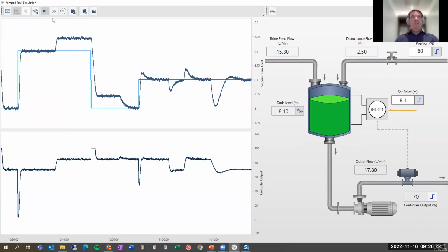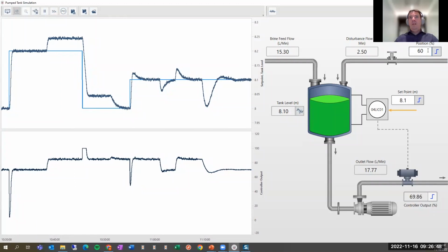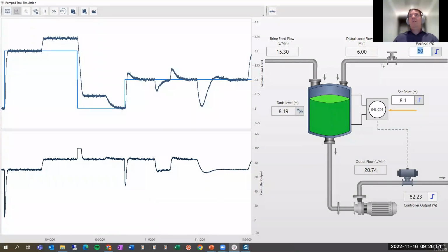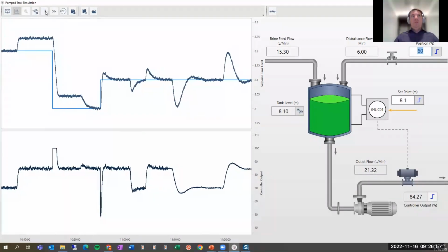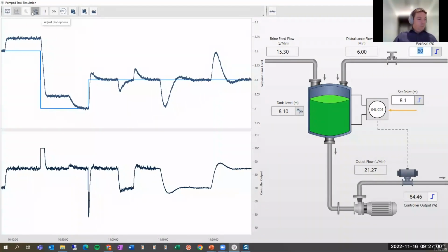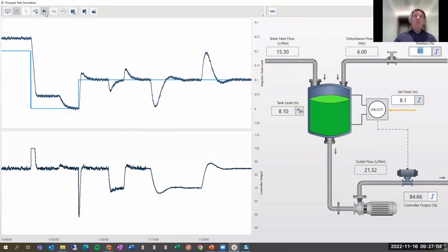So I can go back to 60, and you will see again that, oops, or I need to go to 25. Is that one? Oh no, it's okay. That's the one. So use strong gain, it will help you with set point changes and with load rejection. Derivative will not help you at all in this type of process. And unfortunately, there's an overshoot in a set point change, but as I said, not that many set point changes in level. You will have a good load rejection here with those tunings.